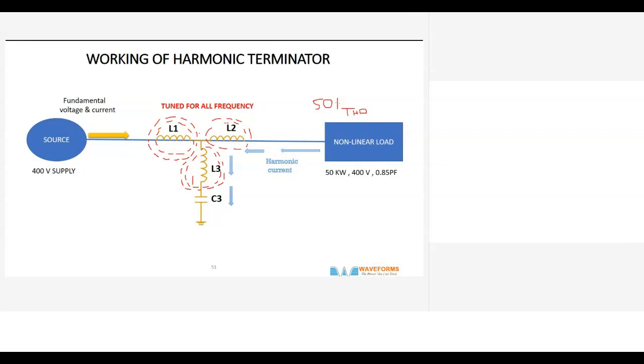And this L2 has another job. This winding is done in reverse, so reverse polarity. Why do we do it? When you have a magnetic flux in a forward direction and a magnetic flux in the reverse, we minimize the voltage drop. It cancels and does not allow voltage drop. Normally, when you have too much inductance in series, voltage drops. That is the principle of an inductor. But that principle is defeated by winding it in a different way to ensure that voltage doesn't drop. So you don't cause any voltage drop, but you cause high impedance for high frequencies or different harmonic orders. Plus, you have a diversion technique employed. You have an inductor and a capacitor.